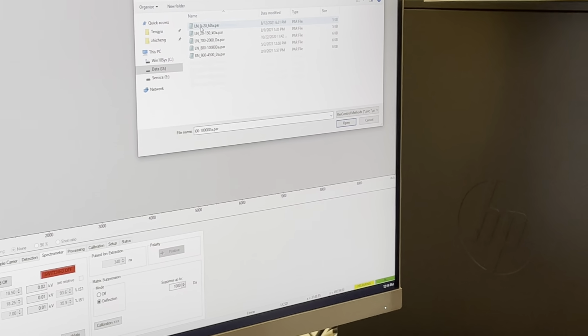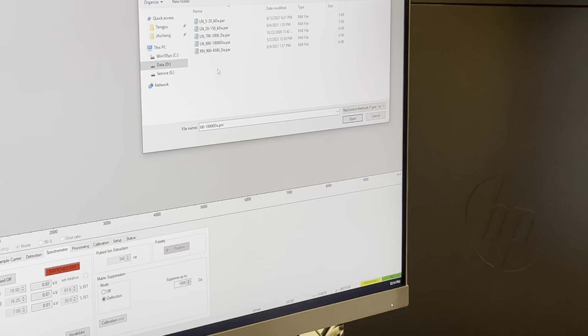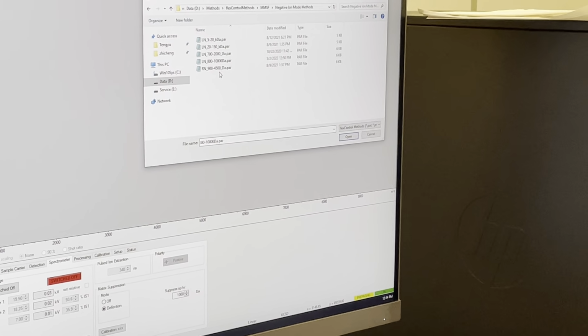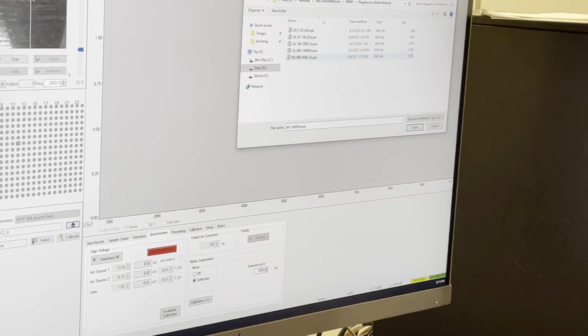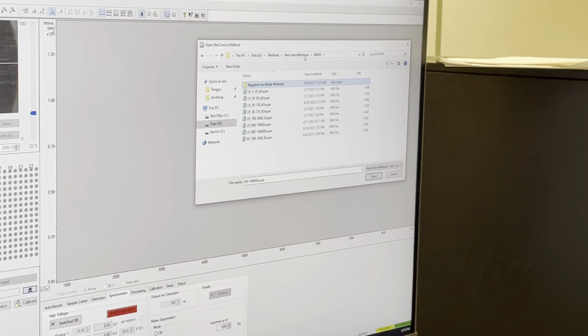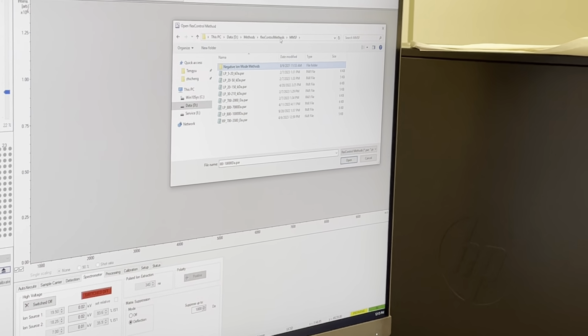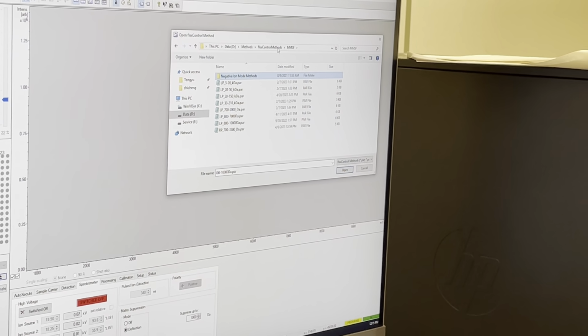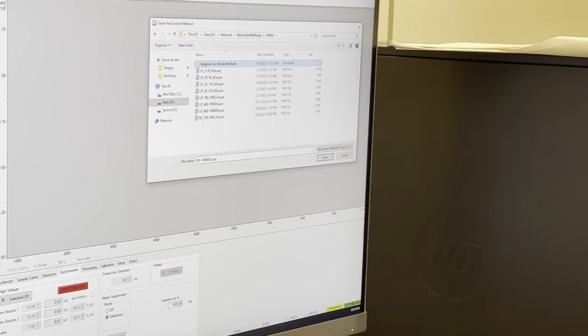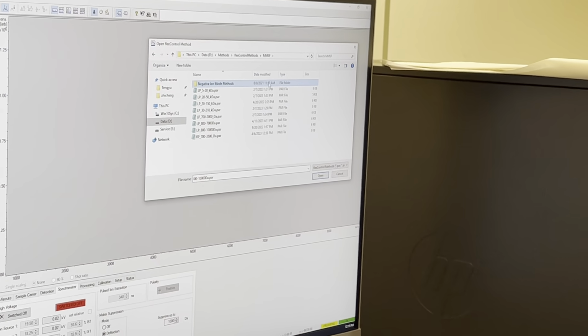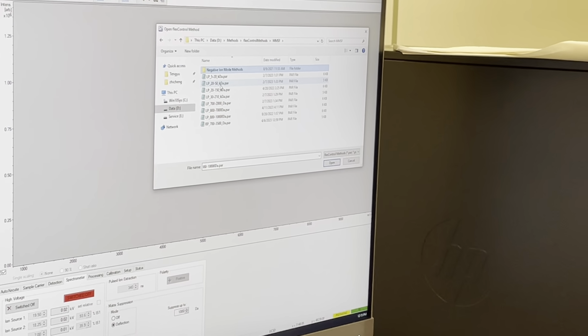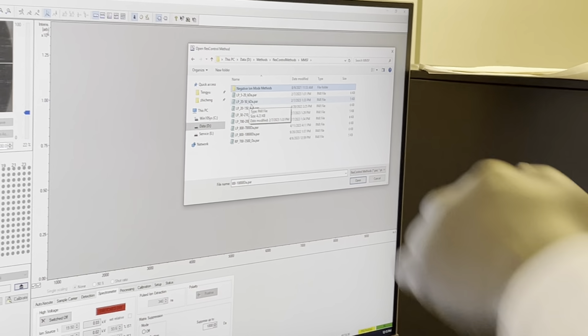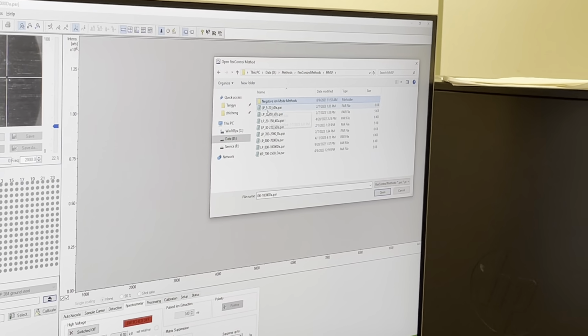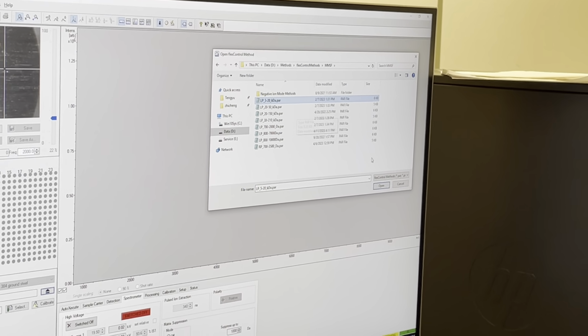But in case you want to do negative ion mode, you have to double click this button. You will see all the negative methods right here. R is reflection, L is linear. You know that, right? Now for the MALDI-TOF, the reflection mode is used for peptides or small molecules. But for protein, always use the L method. LP is the most popular one. So we are going to use the LP 5 to 20K method. Okay, good. Select this method, hit open.